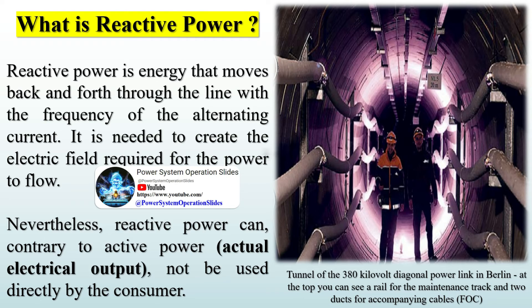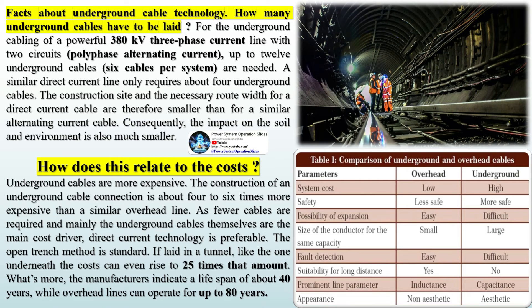Facts about underground cable technology: for the underground cabling of a powerful 380 kV three-phase current line with two circuits, up to 12 underground cables — six cables per system — are needed. A similar direct current line only requires about four underground cables. The construction site and necessary route width for a direct current cable are therefore smaller than for a similar alternating current cable, and the impact on the soil and environment is also much smaller.